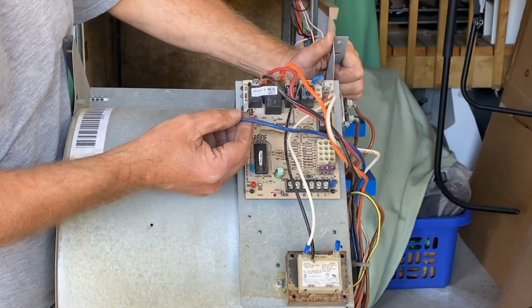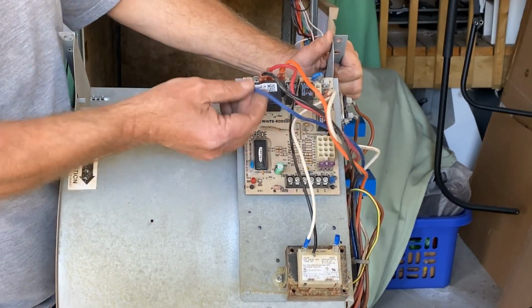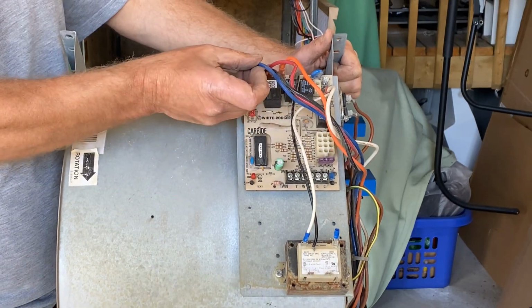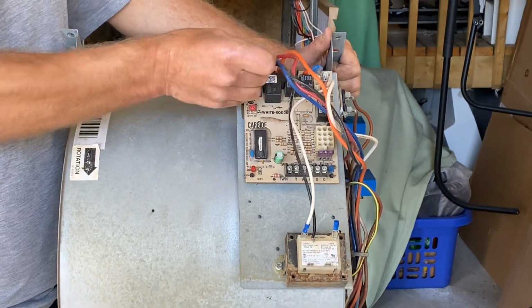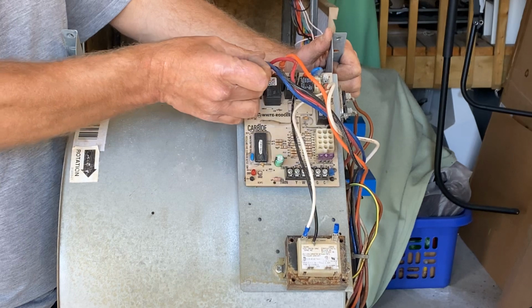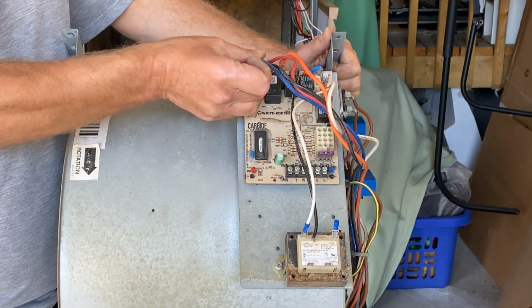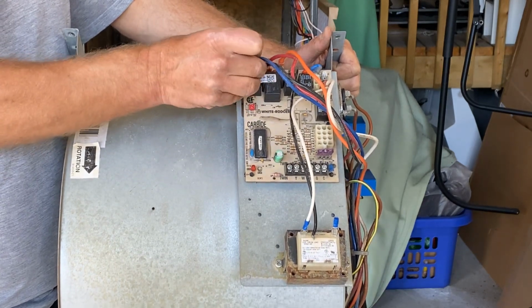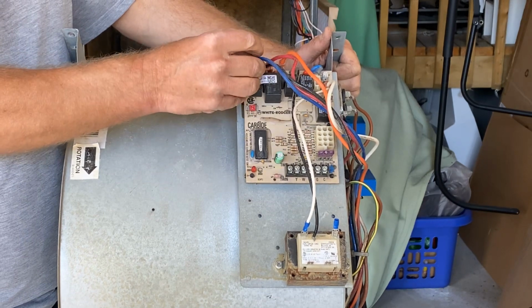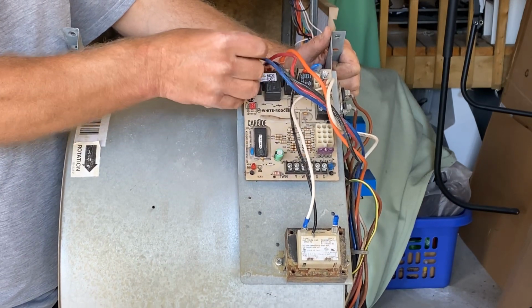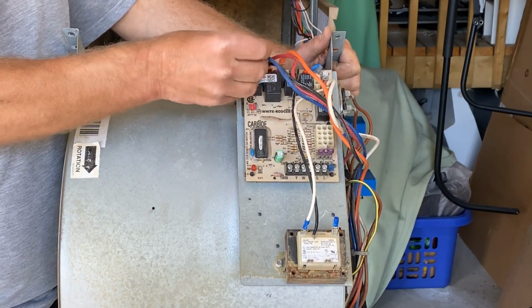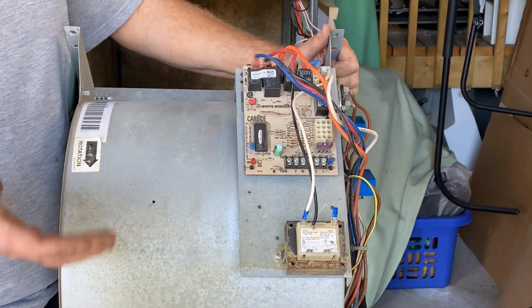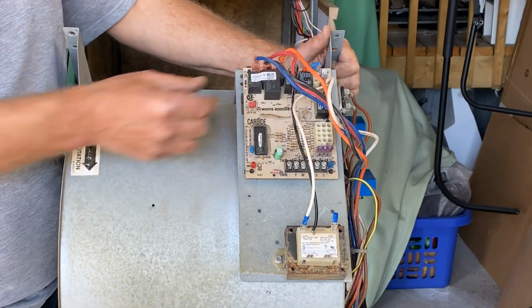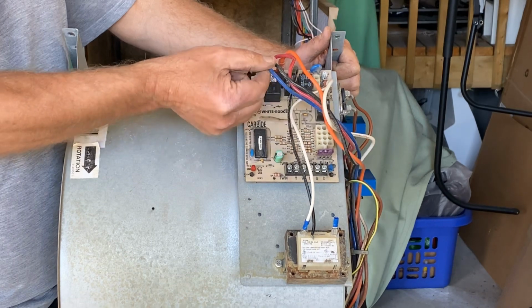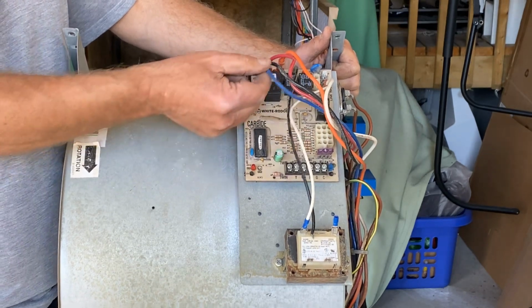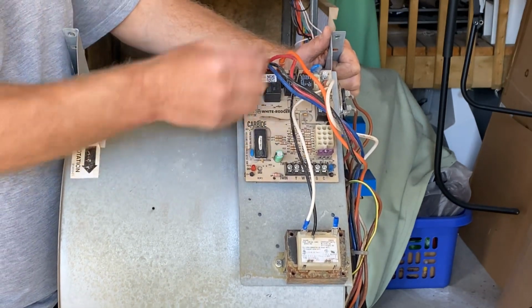I didn't notice this before, but they have low speed on cool. Generally you're going to find that cool is better with high speed, especially with a multi-story house. If it's a single-story house, not such a big deal, but a multi-story house, remember, cold air is heavy, warm air is light. So it's easier for me - I can use a lower speed for heating than I can for cooling, generally speaking.